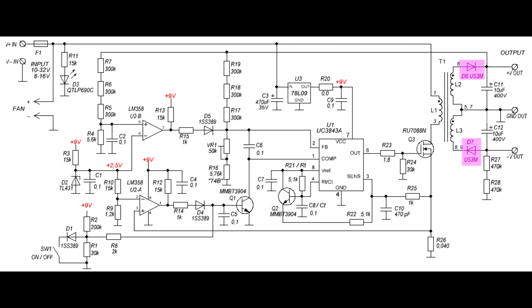Based on the tests that have been done, when the output is loaded, if the output current exceeds a certain level and the circuit has to compensate for coping with the request, the original rectifier diodes have the tendency to short. These are ultra-fast rectifiers rated for 1000 volts, 3 amps.